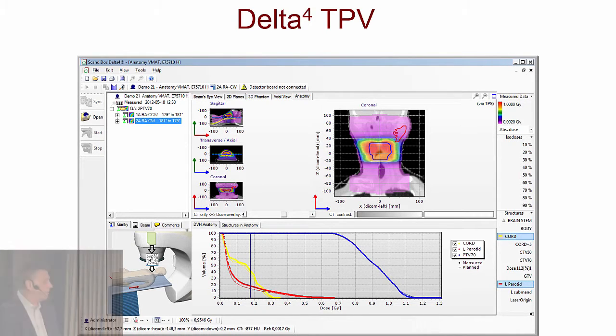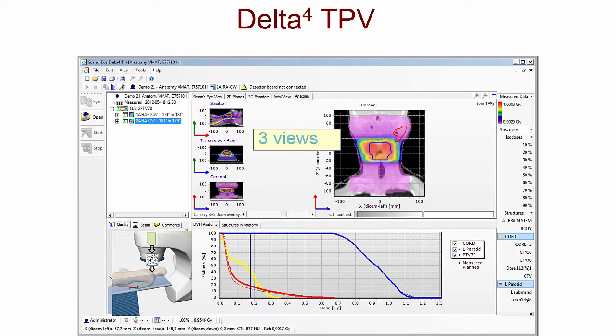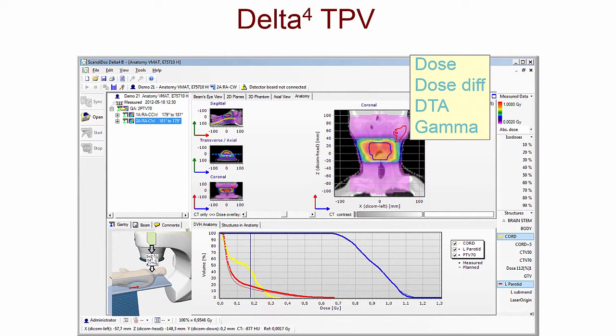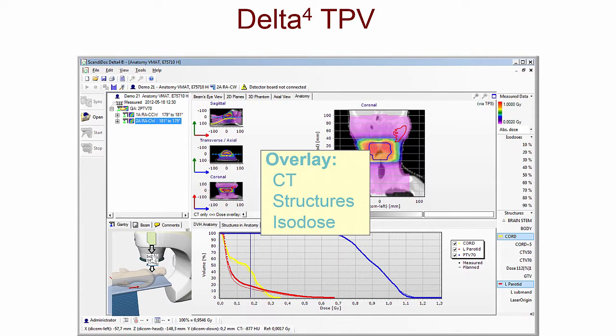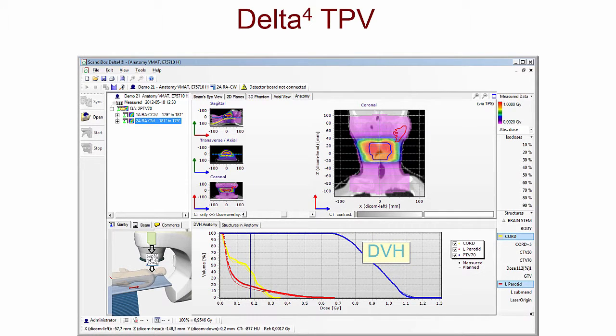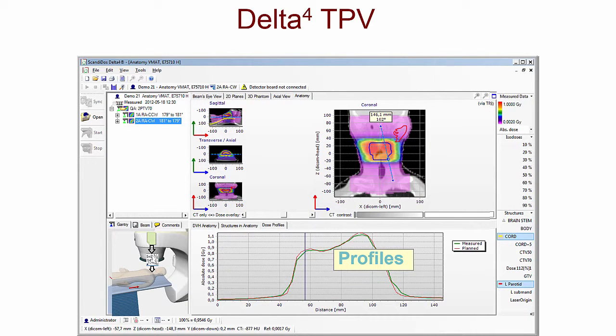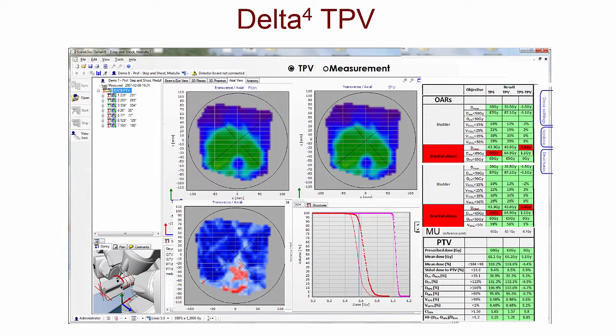It gives you data similar to the measured data, those 3D views. You get the dose difference, the distance to agreement, the gamma index, and you can also overlay the CT and structures and isodoses. And finally, look at the dose volume histograms to verify the clinical relevance and the correctness of the treatment plan. Similar to what you do on measurements, you can also look at profiles. So if you're familiar with Delta4 software, you will feel very familiar using this software for verifying also the treatment planning system correctness.